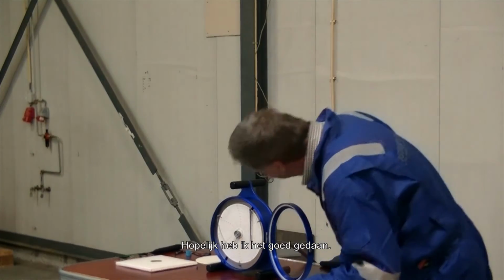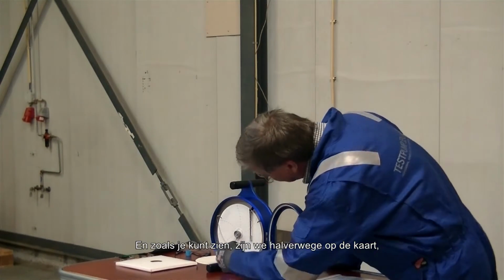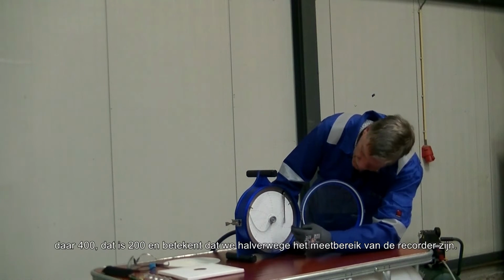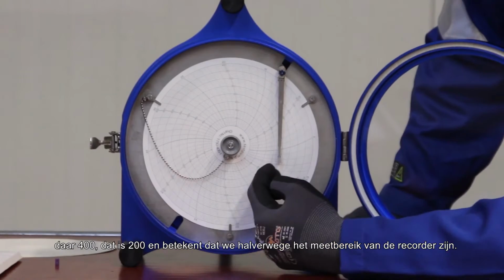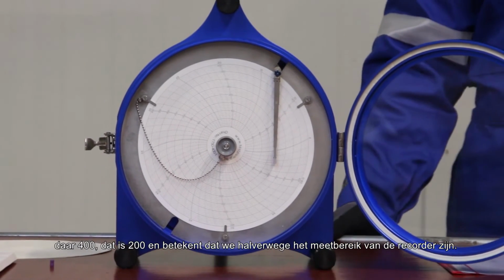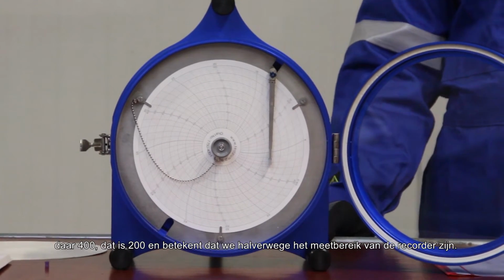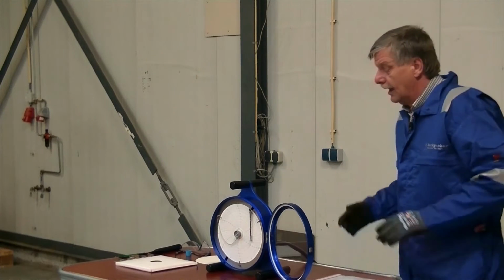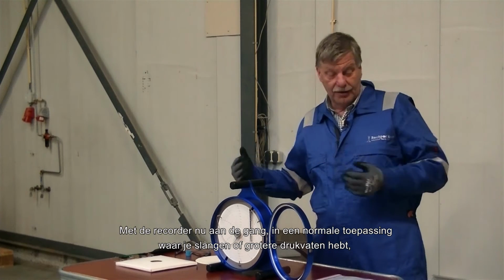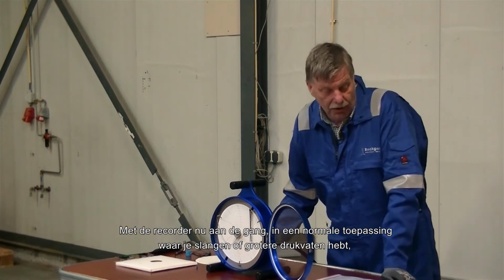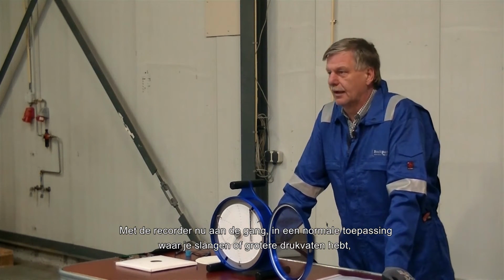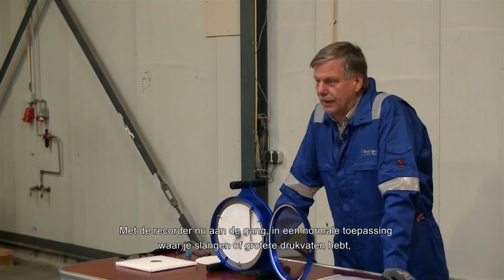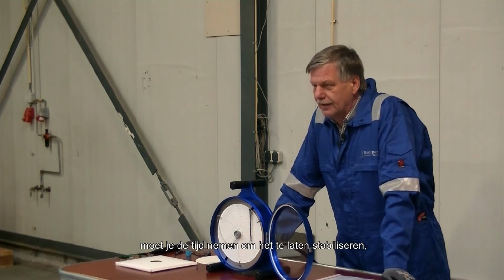Hopefully I've done it right. And as you can see, we're halfway on the chart. Being 400, the 200 means that we're halfway of the range. With the recorder up and running now, in a normal application where you've got hoses or larger pressure vessels, you need to take your time to let it stabilize.